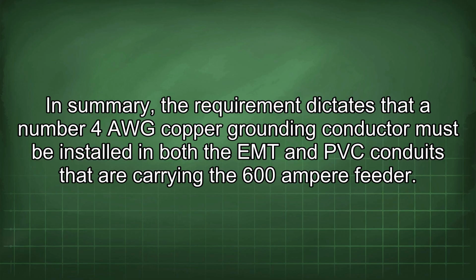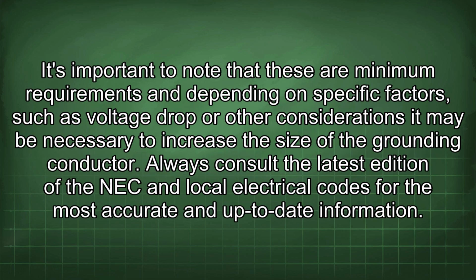In summary, the requirement dictates that a number 4 AWG copper grounding conductor must be installed in both the EMT and PVC conduits that are carrying the 600 ampere feeder. It's important to note that these are minimum requirements, and depending on specific factors, such as voltage drop or other considerations, it may be necessary to increase the size of the grounding conductor.